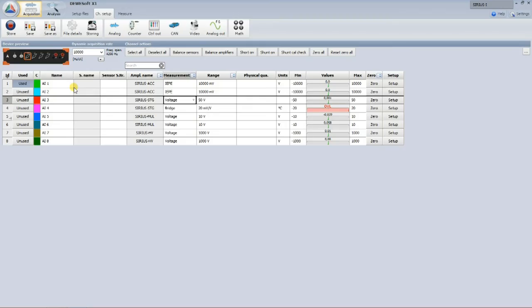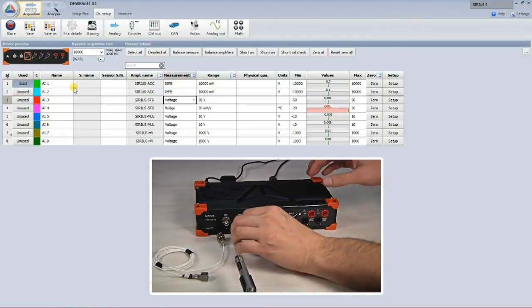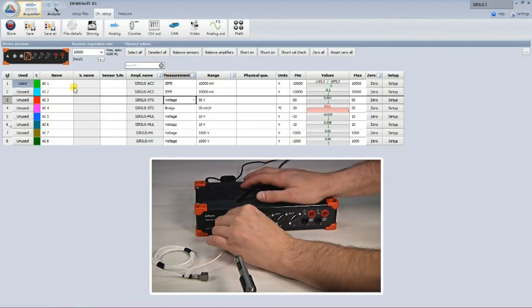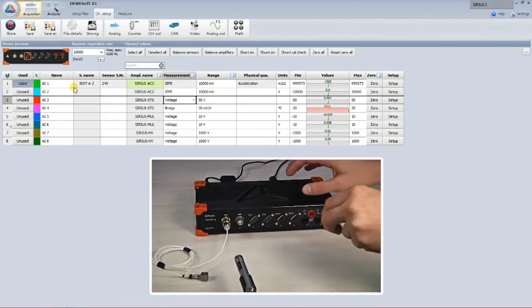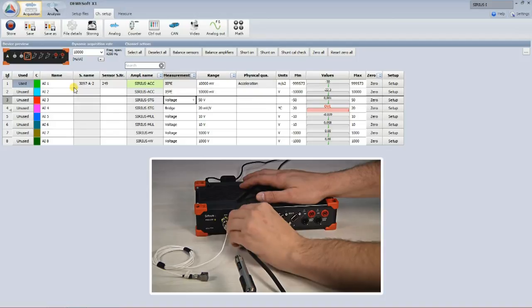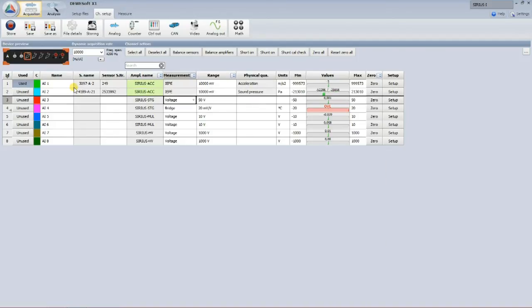To make sure that sensor setup is correct, Sirius features smart sensor interface using TEDS technology. This means that all sensors equipped with TEDS chip will automatically set amplifier settings and scaling for that sensor. It is also very easy to define the sensor.